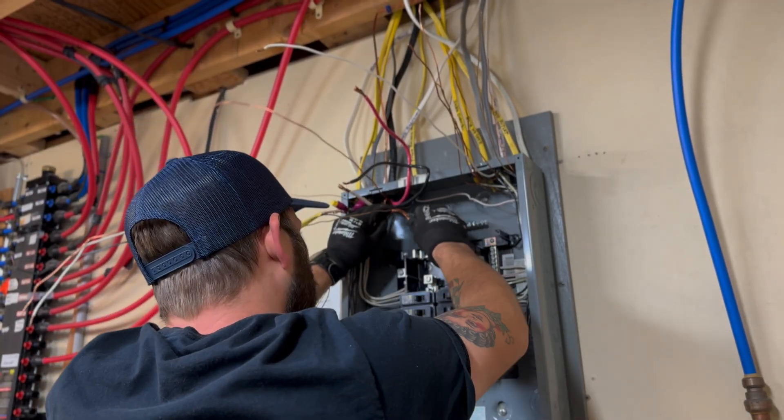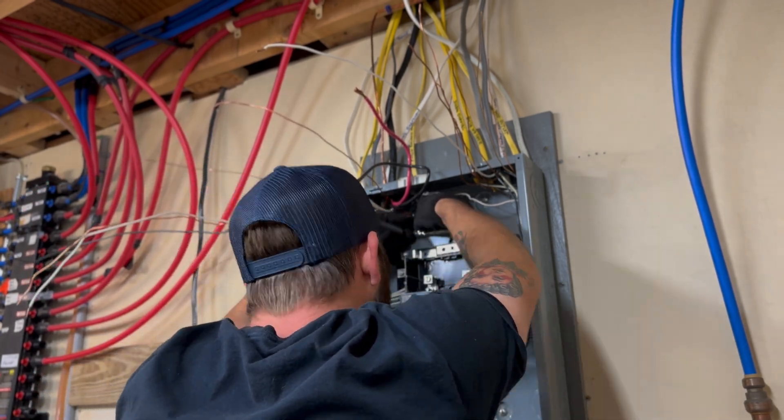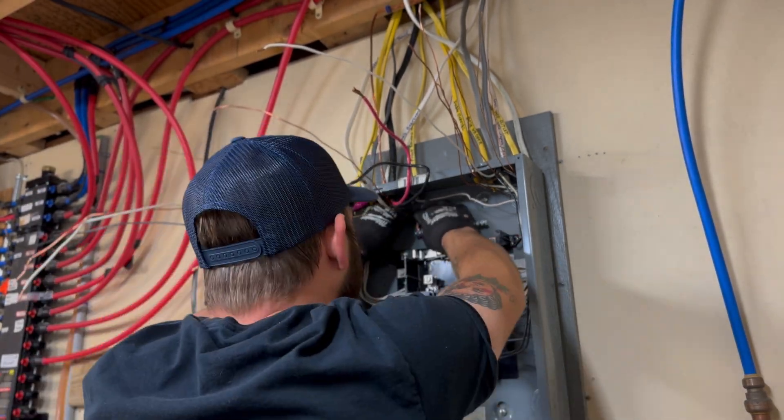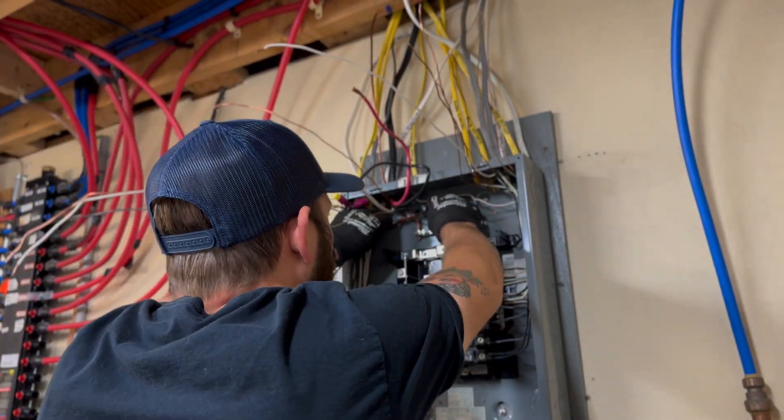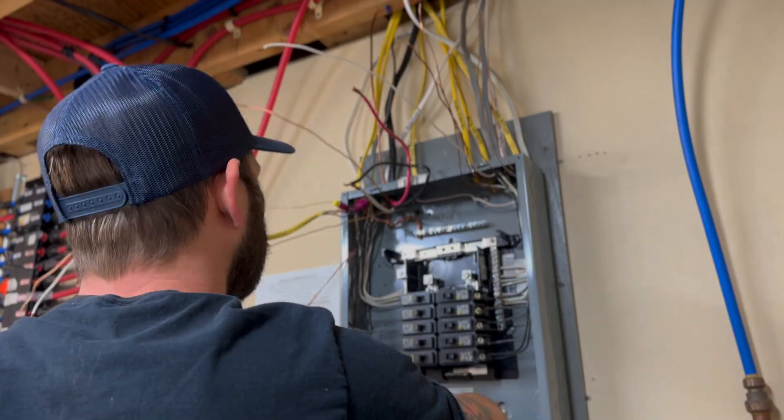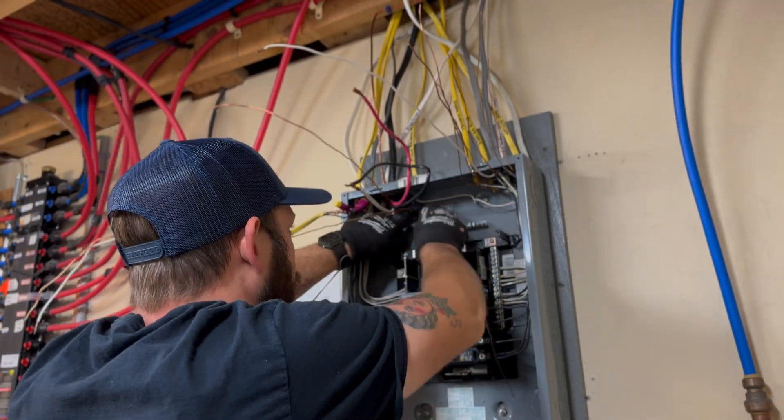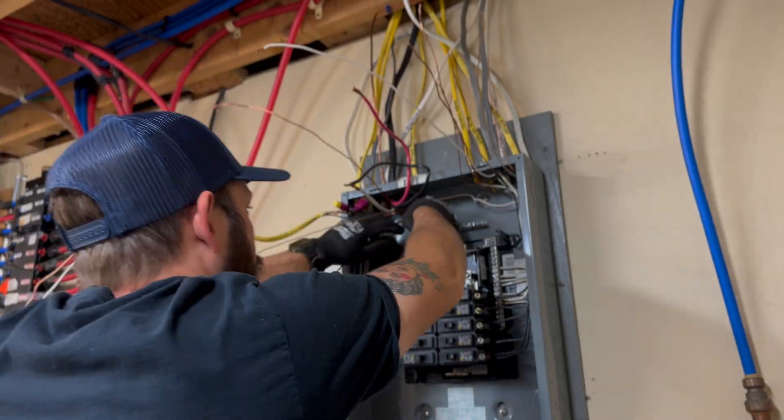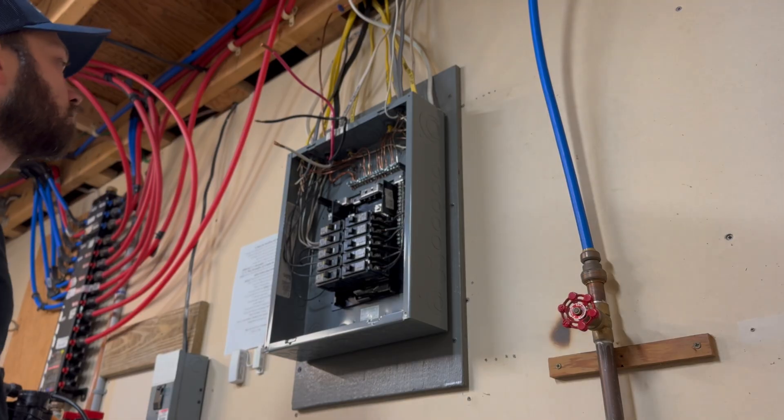And then now we're just working all the grounds back into that ground bar. Once all these got landed comfortably that made sense inside this panel, again ran through and torqued all these down to spec. I believe it was 20 inch-pounds on everything pretty much here.